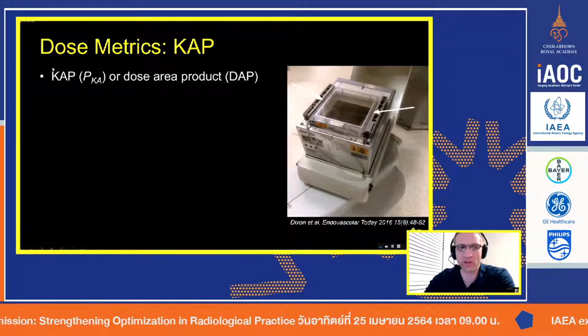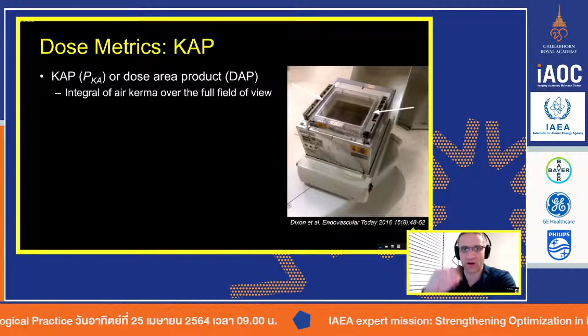What it is, is the sum or integral of air Kerma over the field of view. So whatever field of view you set on your patient while you're doing the fluoroscopy, and you may change it over the course of the procedure, KAP will take into account not only the output, the air Kerma coming out of the machine, but also how much of the patient or the area is being exposed.